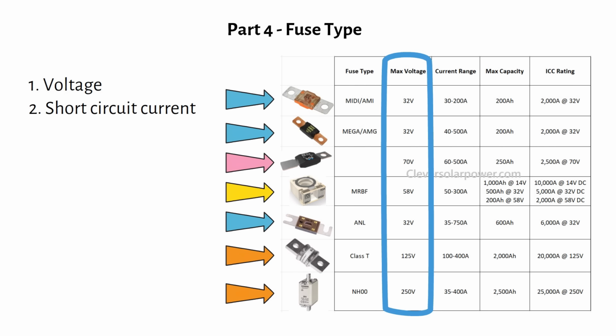Now the second thing you have to check is the short circuit current rating, also called ICC. All that means is, if something shorts out and thousands of amps try to flow, can this fuse actually stop it? Or does it just turn into a welding rod and keep conducting? That rating matters a lot with lithium, because lithium can dump a ridiculous amount of current instantly. Let me show you how high that current can be.